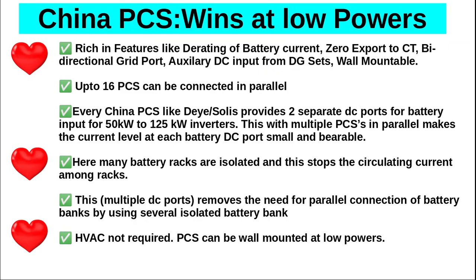have an advantage here because the current is now distributed, and also there will be no circulating current because the battery racks are isolated. This stops the circulating current among the racks. This is a very big advantage in the case of China PCS. These multiple DC ports remove the need for parallel connection of battery banks by using several isolated battery banks. So that is a very clear advantage. That is, we will have a lower probability of fire because of that, because there is no circulating current in this case. Another big advantage in the smaller capacity PCS of China is that the HVAC is not required. You can just wall mount the China PCS. Of course, this is possible only at lower power levels, lower capacity BESS.